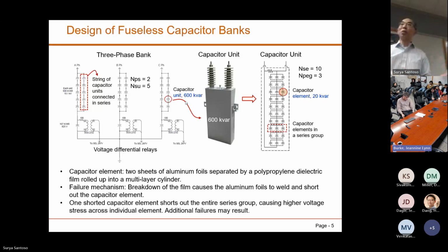So what are the consequences of shorted elements? Remember that in here you can see there are relay circuits, and these are 87 relays, meaning they are differential protection relays. For this particular case, we usually use a voltage differential protection that tries to measure the differential voltage. If the capacitor is healthy, with no shorted element, the differential voltage is 0, because there is a K factor that you can adjust such that the differential voltage is 0.